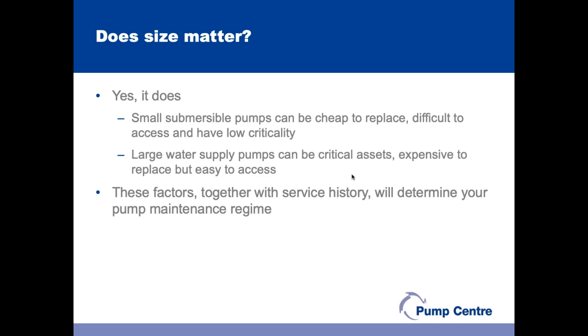And often these pumps, quite rightly, because that's how they were designed, are easy to access. So it makes sense to put effort into maintaining those pumps and visiting them regularly because it's relatively easy to do. So all of these factors, together with some knowledge of the service history, should be used to determine the pump maintenance regime.